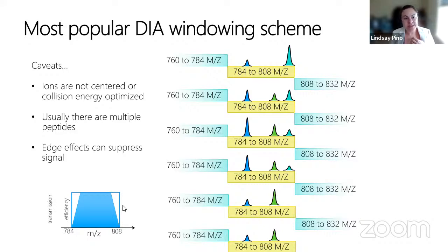Are there benefits to doing slightly overlapping windows for DIA? Absolutely. If you use slightly overlapping windows, if you're on a TOF, having the margins on your windows is good. If you're on an Orbitrap, do not use margins. Instead, do a full stagger, a 50% stagger. That is also discussed in that MCP 2020 paper that I'll make sure I link in the documents.